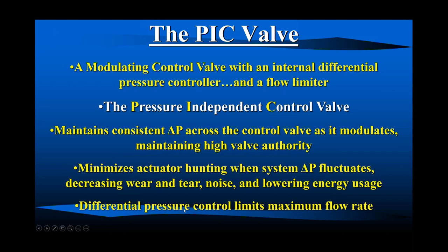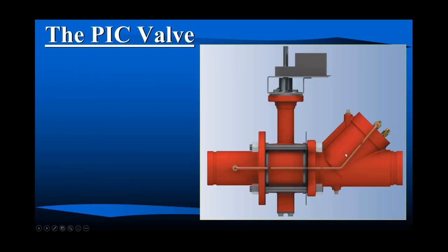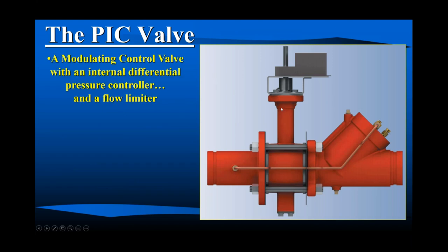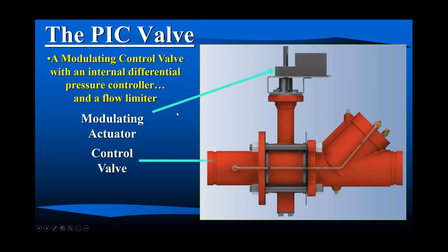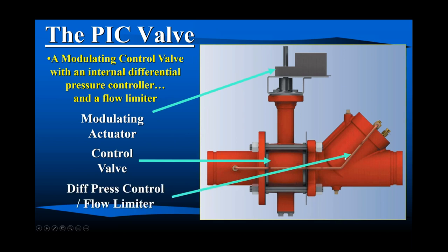It is a flow limiter. This is what it may look like. Modulating control valve, right? Not on, off, modulating control. There's our modulating actuator, our control valve body. And yeah, it looks just like our automatic flow balancing valve. There's a device in there that limits flow.